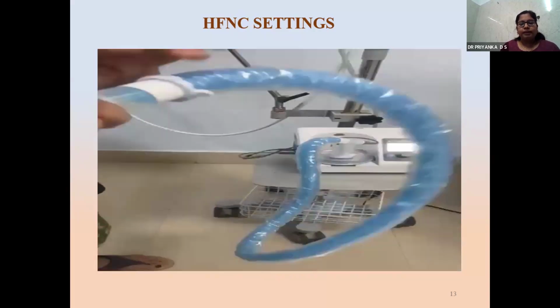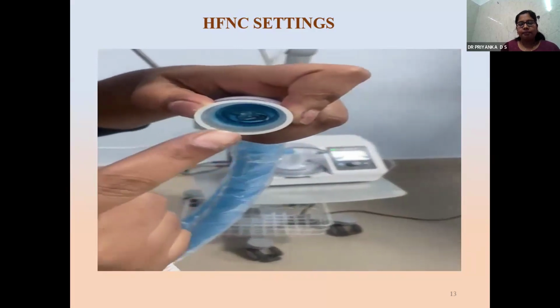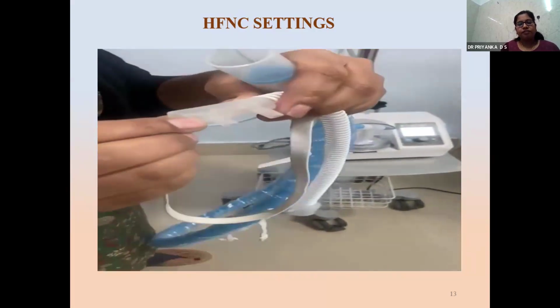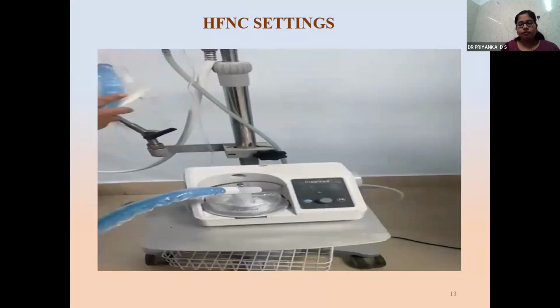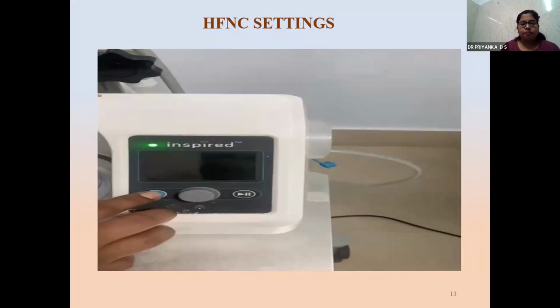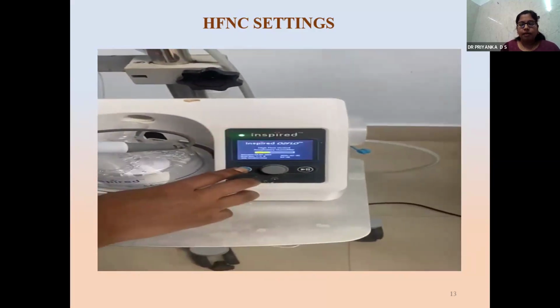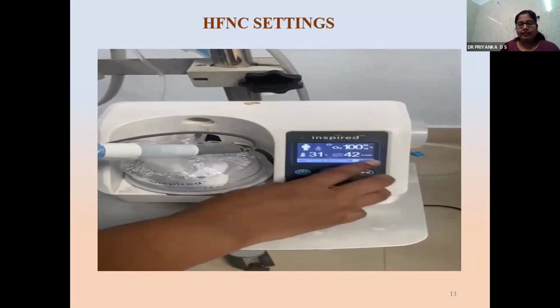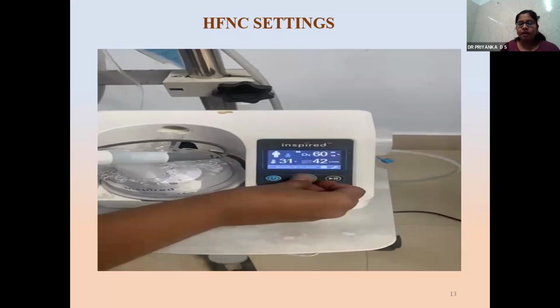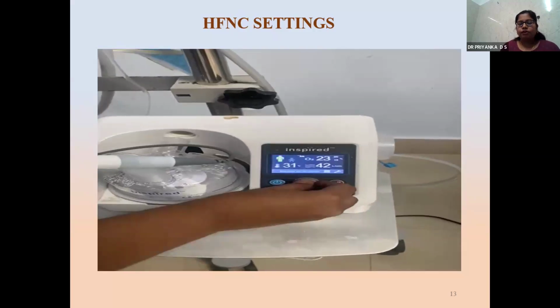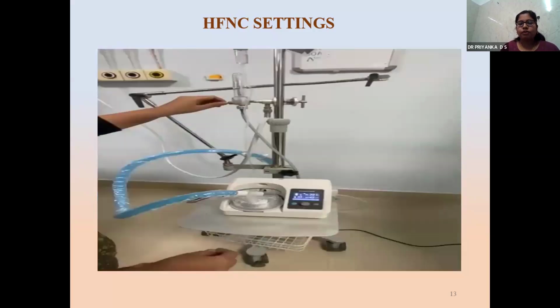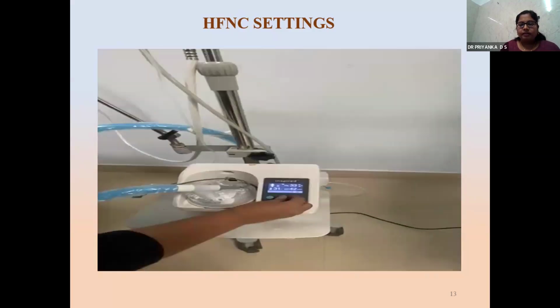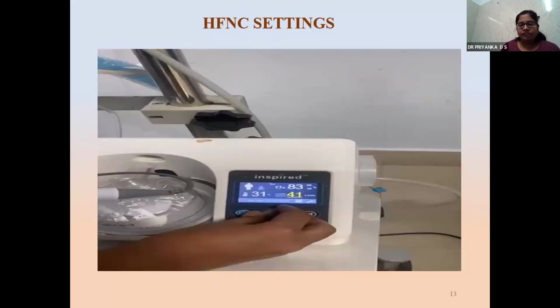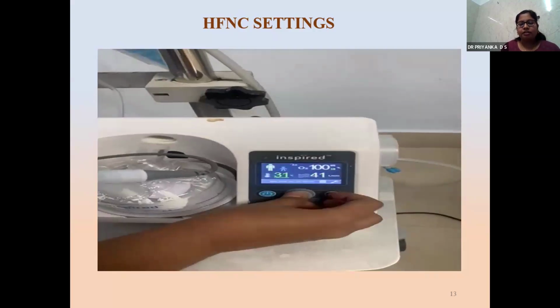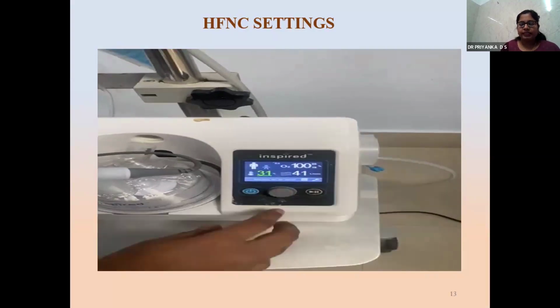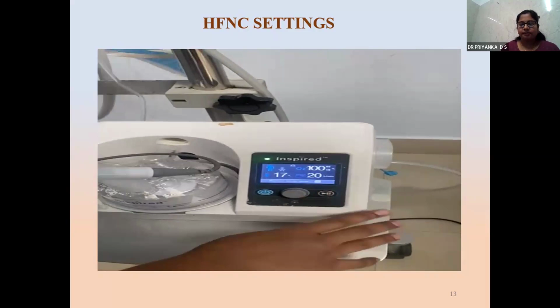This is the inspiratory tubing, which has a temperature probe and heat sensor inside it to maintain the temperature along the flow. This is the patient's interface with a soft and pliable nasal cannula. To switch on this monitor, we have to press this power button for a long time. Basically, it has 4 settings. To unlock this, we have to press the rotary knob over the power button, and then we can set it for adult and pediatric age group. Then to increase the FiO2, we have to switch on the flow meter to achieve a desired FiO2. Then we can increase or decrease the flow rate according to the patient's requirement from 10 to 60 liters per minute, and the temperature according to the patient's body temperature. Once all the 4 settings are done, we have to press this button to start the HFNC.